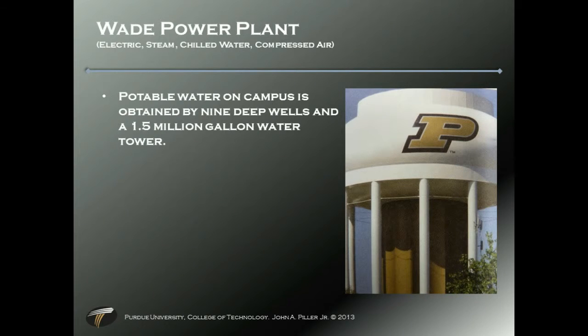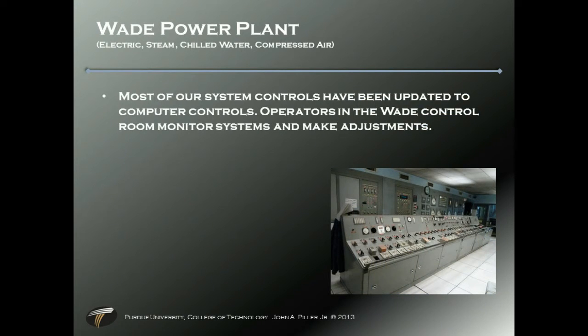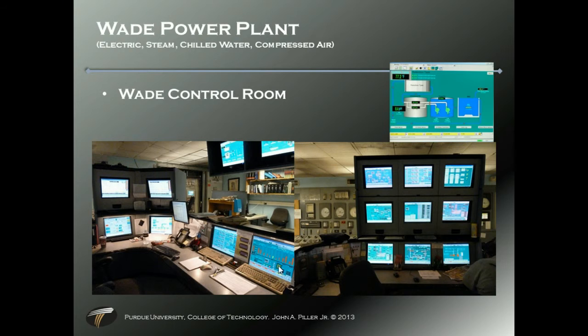Steam is produced using water, which is constantly monitored. The steam that runs the equipment is also USDA approved steam for cooking on campus. So we need clean steam for 2 reasons. A, it's cooking things on campus, and so there's issues with that. And then also, when you're using steam to run through all those tubes, you need clean and pure water with no impurities so that it doesn't cause lime buildup and issues across the board there, which would eventually cause clogging and no water flow, and then that pipe melts, and then bad things will happen to your boiler if that goes down.